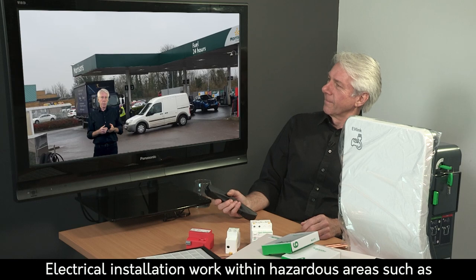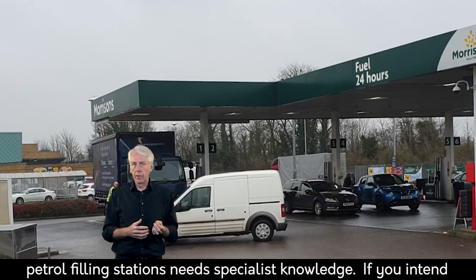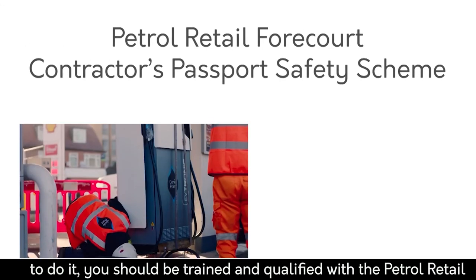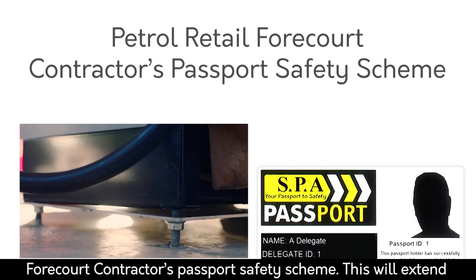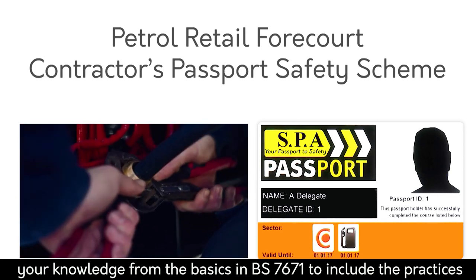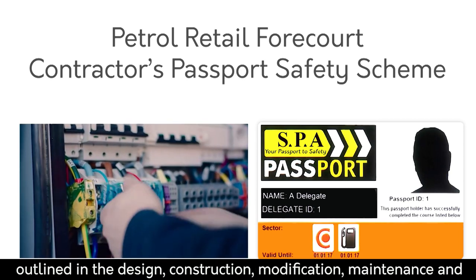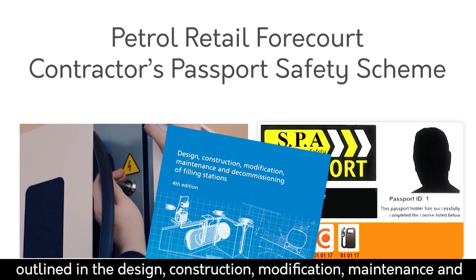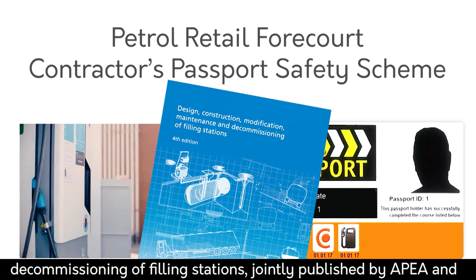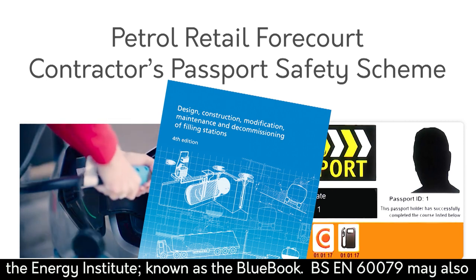Electrical installation work within hazardous areas, such as petrol filling stations, needs specialist knowledge. If you intend to do it, you should be trained and qualified with the Petrol Retail Forecourt Contractors Passport Safety Scheme. This will extend your knowledge from the basics of BS 7671 to include the practices outlined in the design, construction, modification, maintenance and decommissioning of filling stations, jointly published by APEA and the Energy Institute and known as the Blue Book.